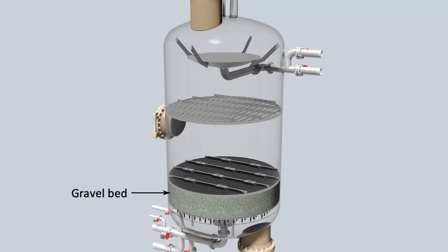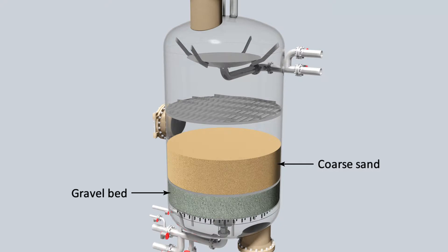The bed is composed of 18 inches of gravel, 30 inches of coarse sand, and 30 inches of fine sand, resulting in a 60 inch layer of effective media filtration.